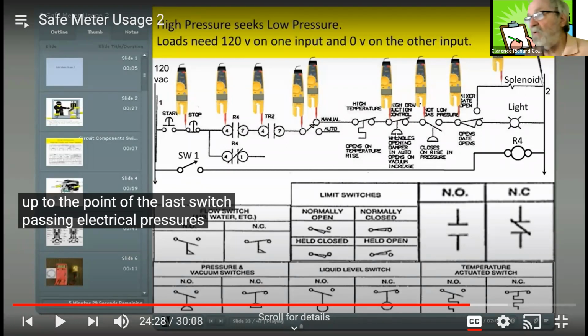Then we've got a pressure switch here. This might be the suction. Might be your Photohelic. Our suction can't be too high. If our suction is too high, it will open it up. So maybe we have to be under 1/10 of an inch of suction there in order to get past that. Now we go to our gas pressure here. This is in our manifold. This is our low gas pressure. If our pressure gets too low, it's going to open up. So we have to have adequate pressure. That's going to close to get that 110 volts there.